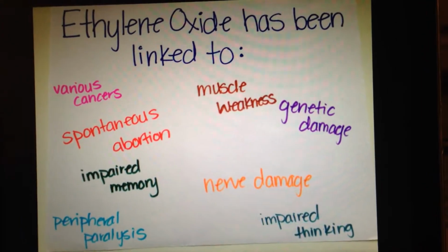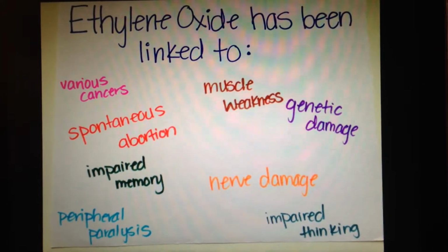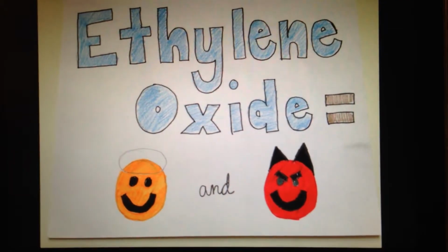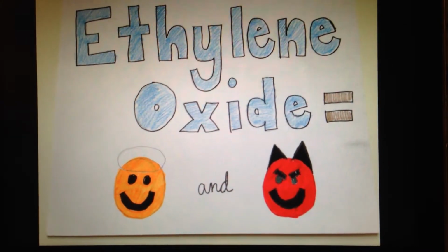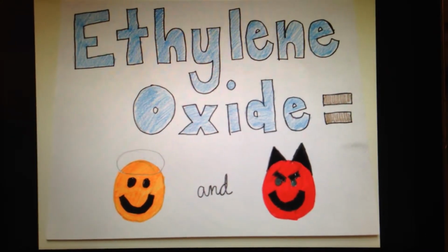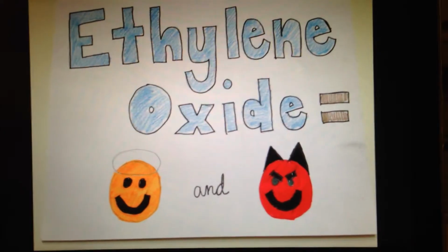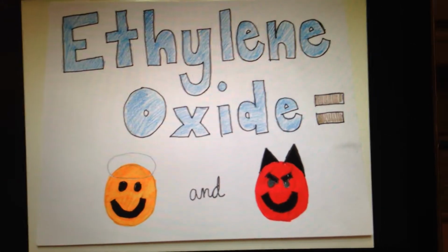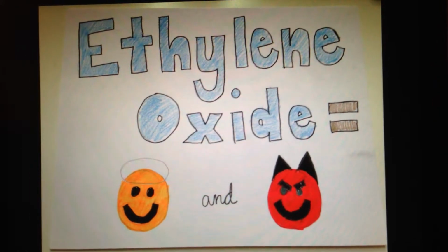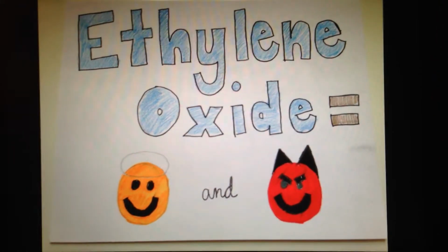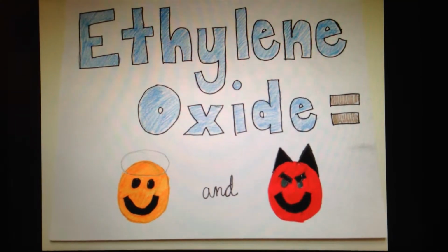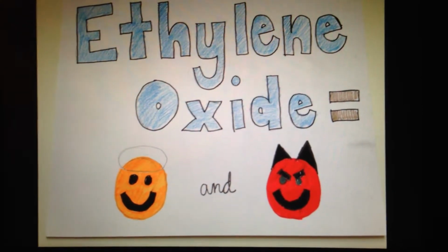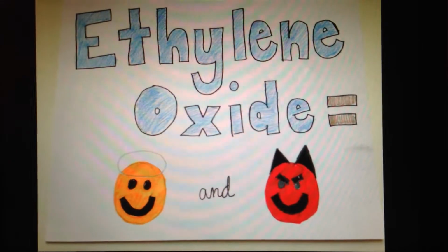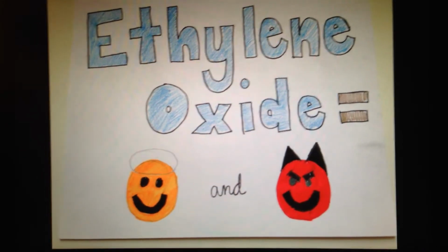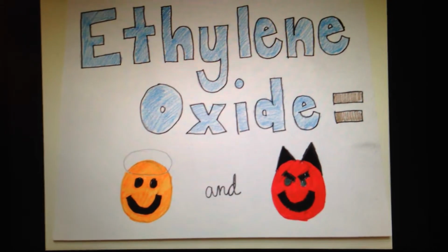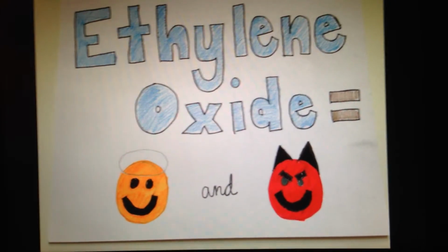Since this gas is so toxic, that's why aeration, the last step in the ethylene oxide process, is so important, because in that step it removes all of the excess ethylene oxide from the package and the product. By doing so, once you come in contact with the package and product, there is a good chance that the ethylene oxide will not be there anymore, which is why you are able to handle it and not have these symptoms.